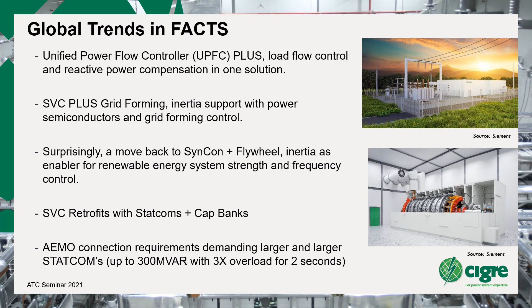There are certainly SVC retrofits, tending now to be with StatComs and cap banks purely from an economic point of view. And in terms of AEMO, connection requirements are demanding larger and larger StatComs to get model approval to connect to the grid in Australia.